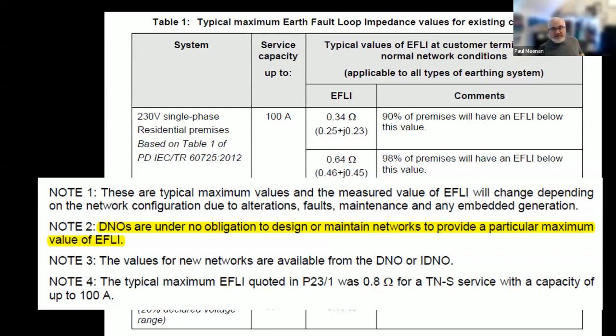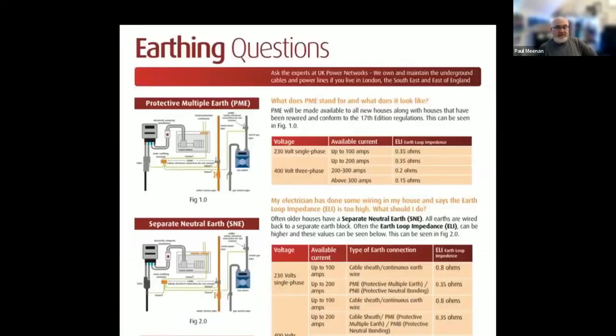One of the more scary points in the UK is note 2. Distribution network operators are under no obligation to design or maintain networks to provide a particular maximum value of earth loop impedance. However, under our electrical safety quality continuity regulations, they are obliged to maintain the earthing. So a little bit of contradiction there, and it makes it very grey. Always an interesting debate with your network supplier, for sure. But some companies will publish very simple guides to earth loop impedance, maximum values, 0.35, depending on the level of energy, 0.8, their standard values for the different earthing systems.